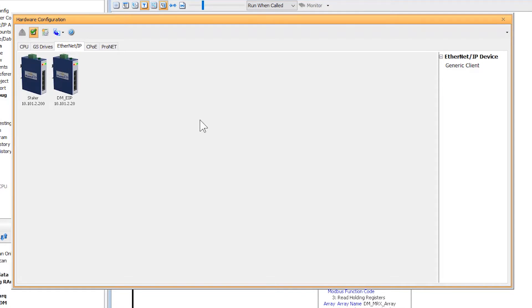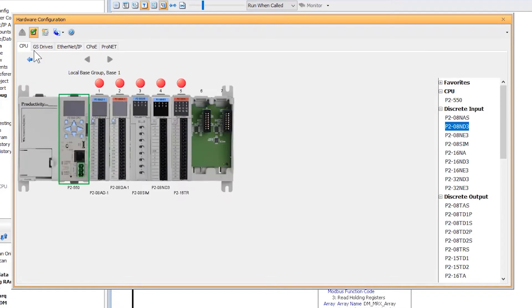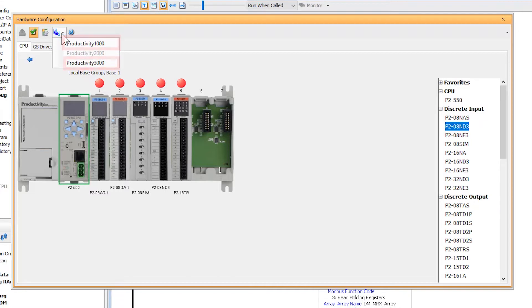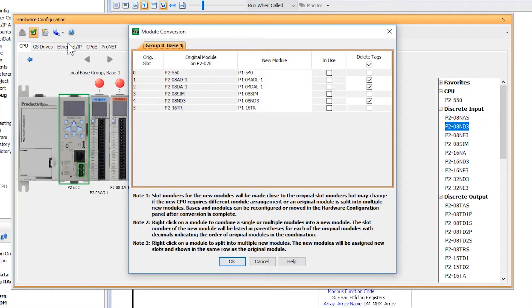Now to begin the conversion process, be right here in the hardware configuration and then select this button. Since this is a P2000 project, you have the option to either convert to a P3000 or a P1000 series. I am going to select the P1000 project conversion. Once I select that, you will see this dialog. Now for this example, everything is fairly straightforward other than the analog modules.